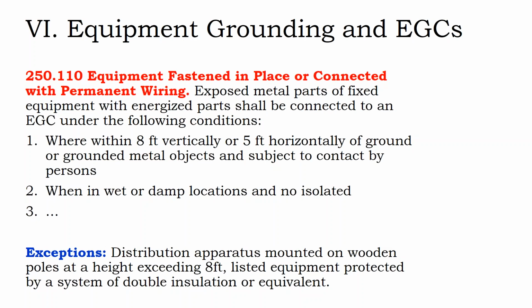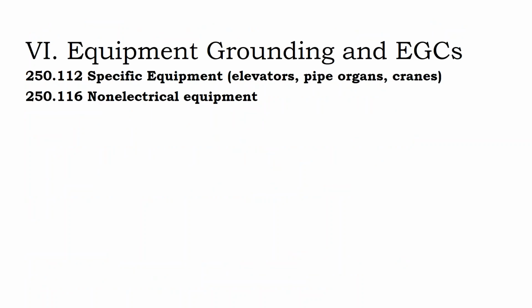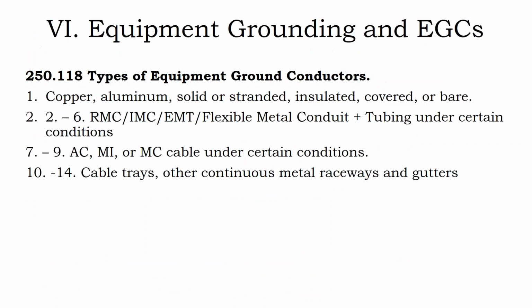So just in general, if you're installing metal equipment, you have energized wires inside that equipment, that metal equipment frame is going to be connected to your grounding system. And while it is possible to have your metal conduit qualify as your equipment ground conductor, what is more common is just to run an equipment ground conductor cable along with your solar array, so you don't have to worry about the exceptions.